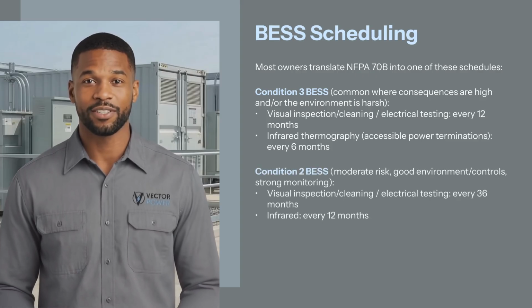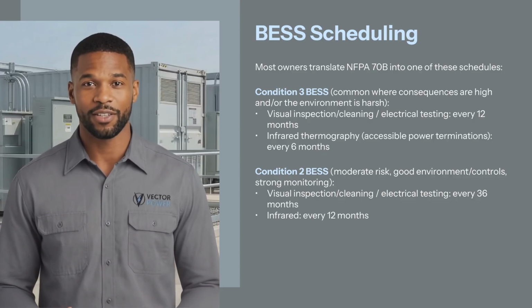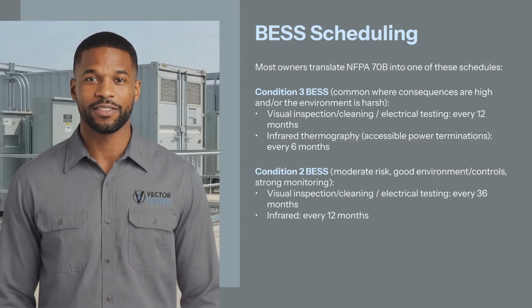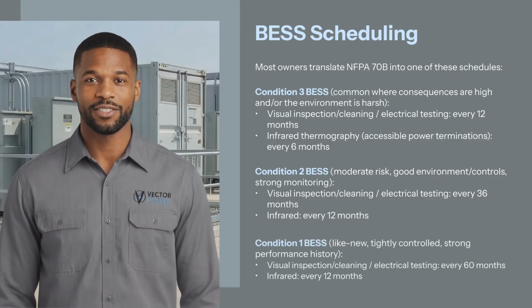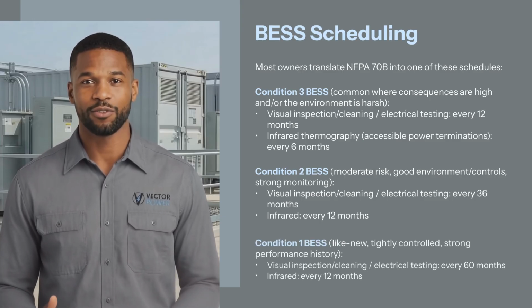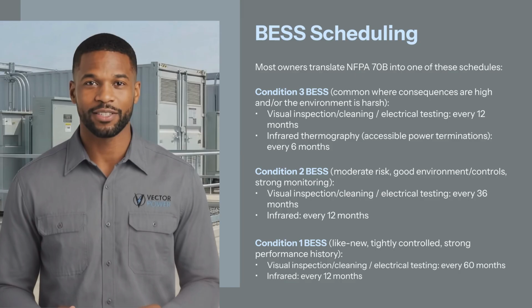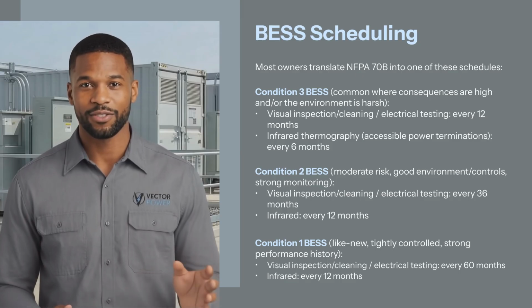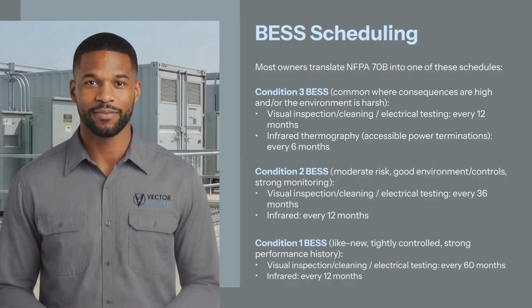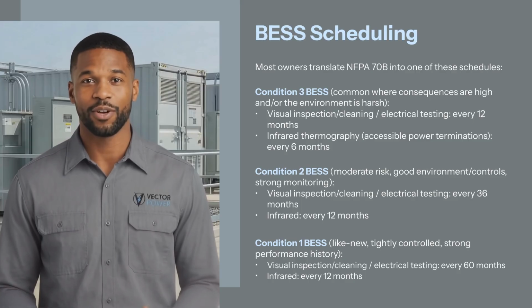Battery energy storage system, moderate risk, good environment and controls, strong monitoring. Visual inspection, cleaning, and electrical testing every 36 months. Infrared, every 12 months. Condition 1, battery energy storage system like new, tightly controlled, strong performance history. Visual inspection, cleaning, and electrical testing every 60 months. Infrared, every 12 months.